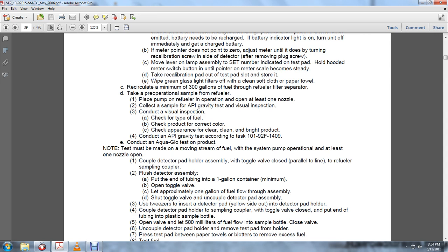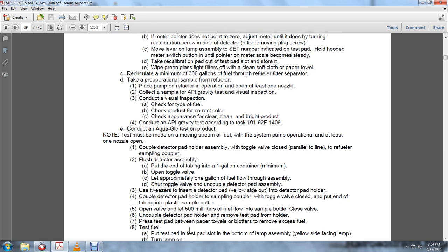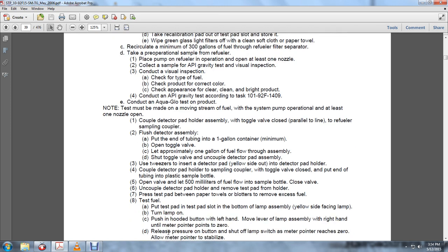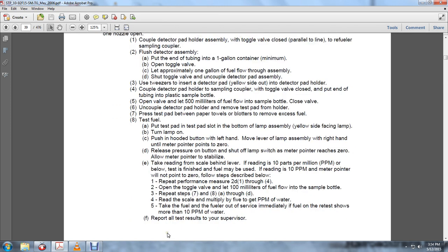Use the tweezers to insert the detector pad, yellow side out, into the detector pad holder. Couple the detector pad holder to the sampling coupler with the toggle valve closed and put the end of the tubing into the plastic sample bottle. Open the valve and let at least 500 milliliters of fuel flow into the sample bottle. Close the valve, uncouple the detector pad holder, and remove the test pad. Press the test pad between paper towels to remove the excess fuel. 8. Test the fuel.